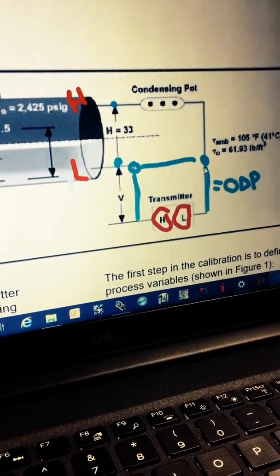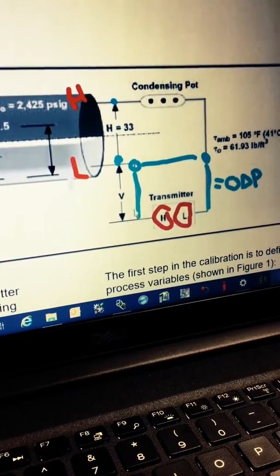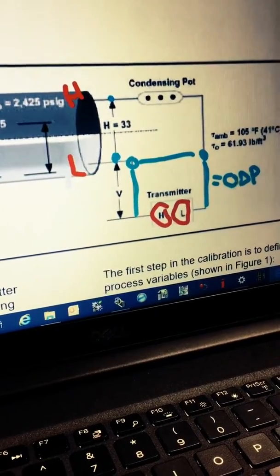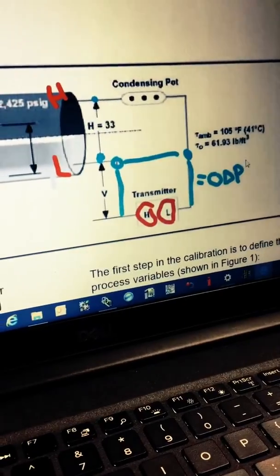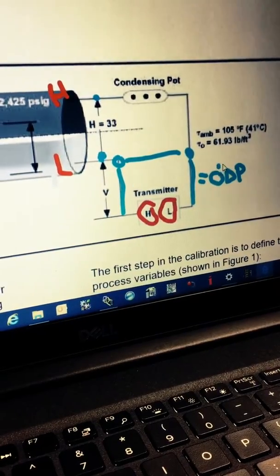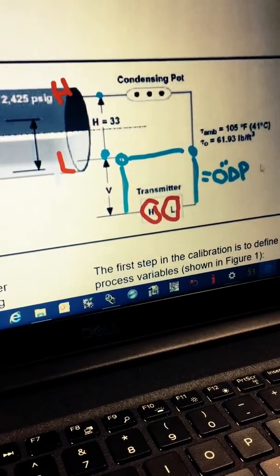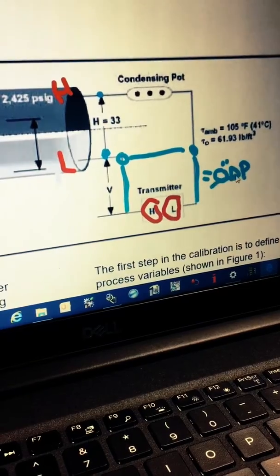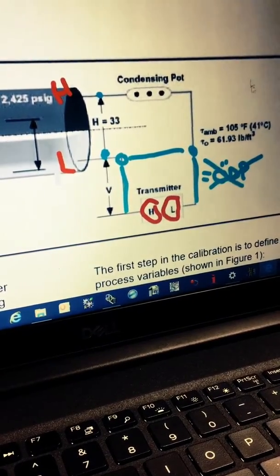So we're basically going to just say that that's zero differential from those points down to the transmitter. And what we're really going to look at is the difference from the low tap of the drum to the high tap of the drum. So we got a zero DP between that lowest point down to the transmitter.